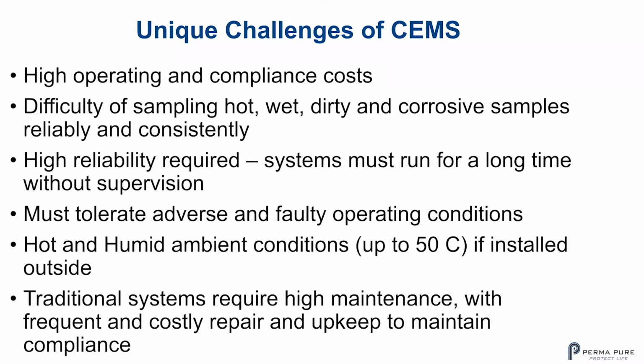It's just not easy. You have a high reliability required. The systems must run for a long time without supervision. Again, it's a cost center. It's not a profit center. So the systems must tolerate adverse and faulty operating conditions. Operating conditions sometimes change at plants if there's a challenge, and you want to make sure the sample conditioning system can handle that. You also have the possibility of operating in hot and humid ambient conditions up to 50 degrees C, installed outside. Traditional systems require high maintenance with frequent and costly repair and upkeep to maintain compliance.